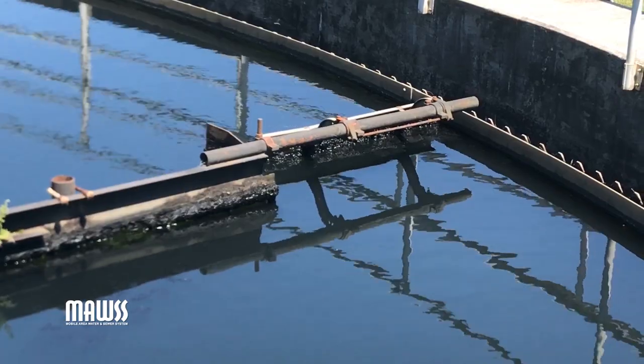And when you do, we vacuum that. I guess the best way to describe it is similar to a pool vacuum for those that wouldn't know, and we put it into a trough and send it down to a thickener that's in the dewatering facility here on plant premises. That thickener has a cone-shaped bottom, and the solids there settle to the bottom. We add a polymer to it to settle that out even more. It's not part of your drinking water process. It's simply, at that point, just dewatering.